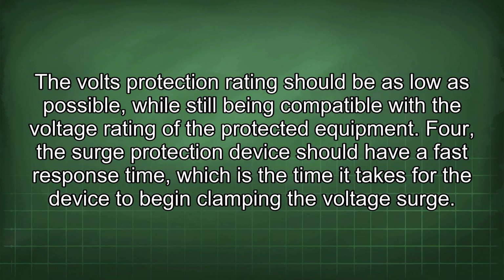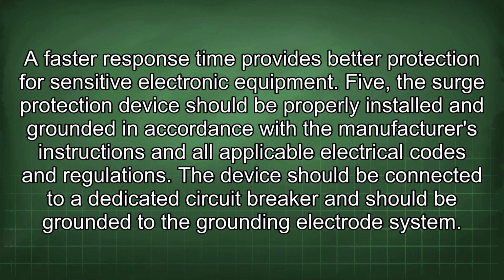The volts protection rating should be as low as possible, while still being compatible with the voltage rating of the protected equipment. 4. The surge protection device should have a fast response time, which is the time it takes for the device to begin clamping the voltage surge. A faster response time provides better protection for sensitive electronic equipment.